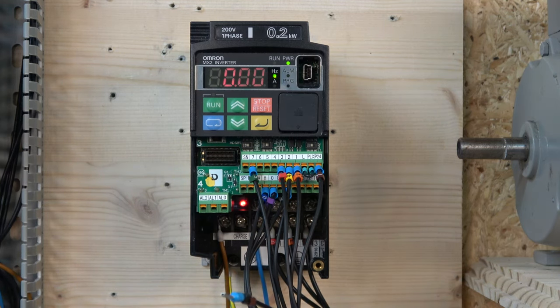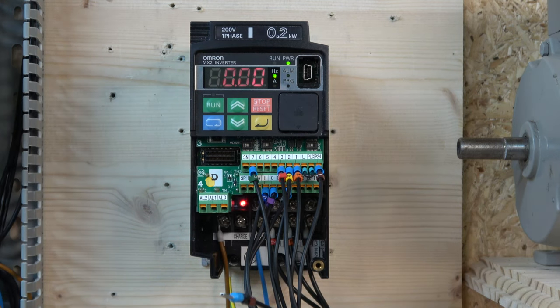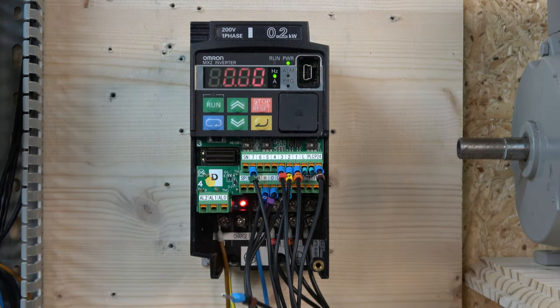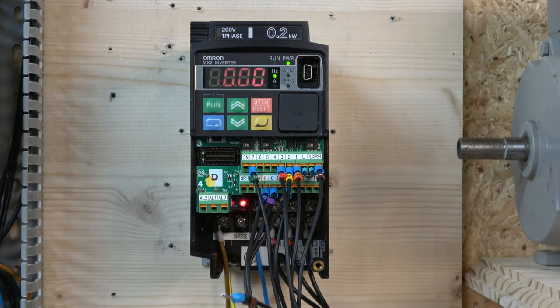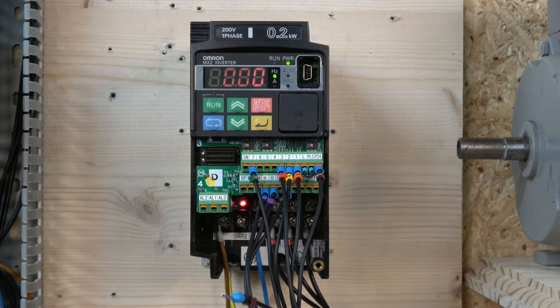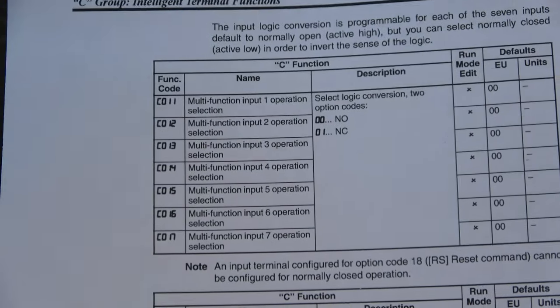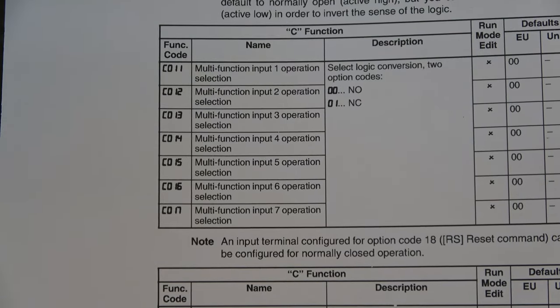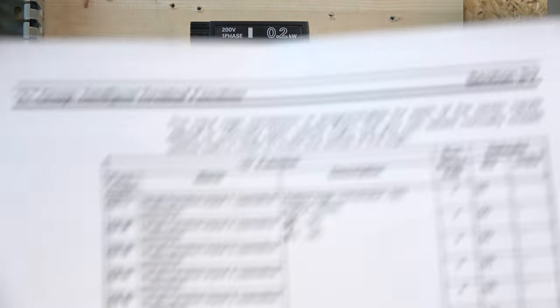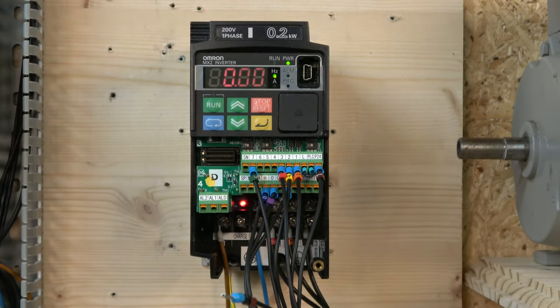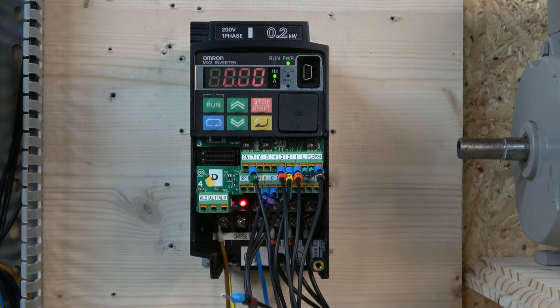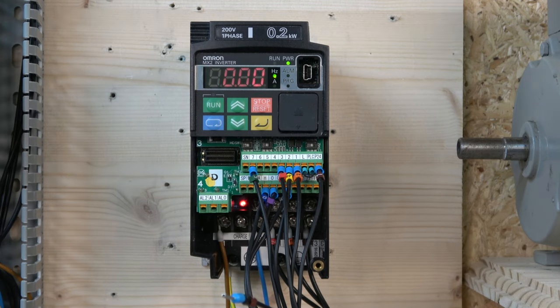When it comes down to what I just did for external trip, as you can see I have permanently sending signal back down to terminal 3. By default terminal 3 is normally open contact, so when it receives power it would go off and basically trip out. But as you can see now it's in reverse. To do that, you can actually reverse your switches, which is on page 154 in the manual. As you can see down here we can change any of the multi-functional inputs to work as normally open or normally closed contacts. So all I did is change C13 to normally closed so now it can operate with normally closed switch on it.